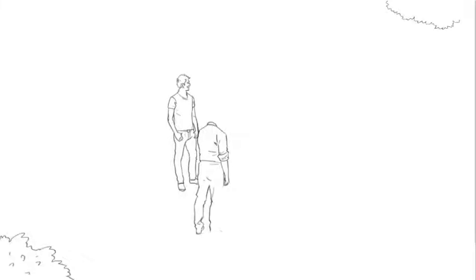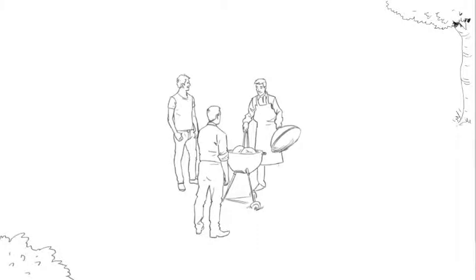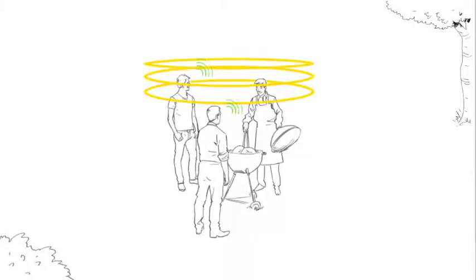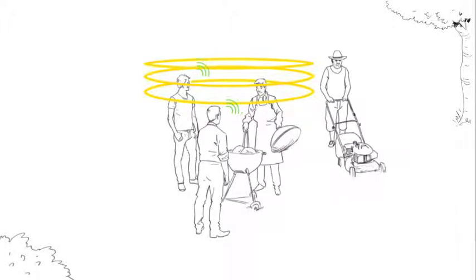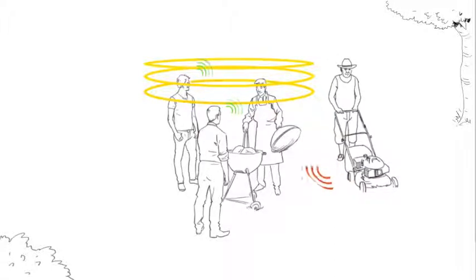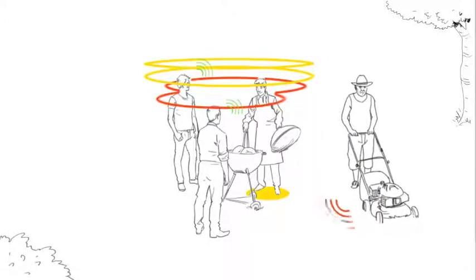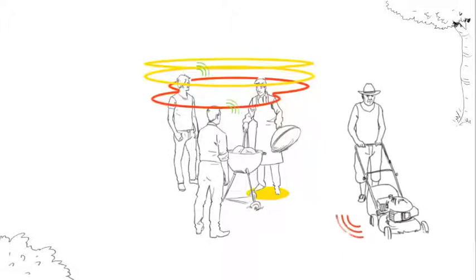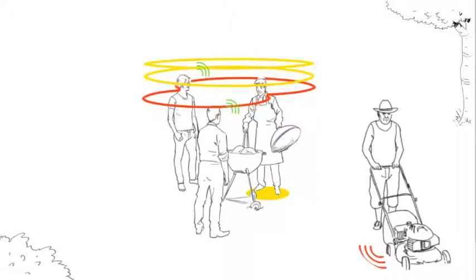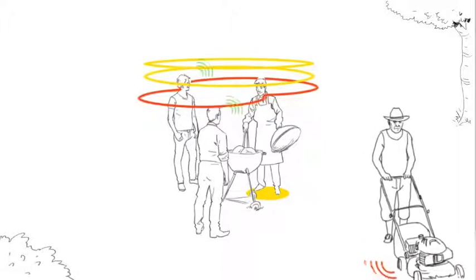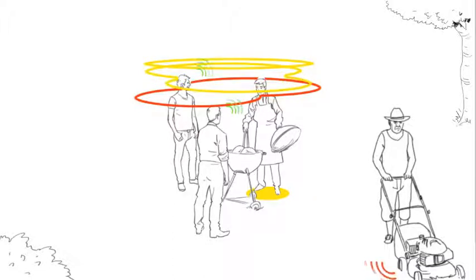Speech-focused directionality also monitors all surrounding sounds like radar. When there is no noise, the device will pick up sounds from all directions. However, when a noise source is detected, the device will automatically track and trace the noise source and form a special sound beam to reduce the intensity of the noise, keeping its focus on speech.